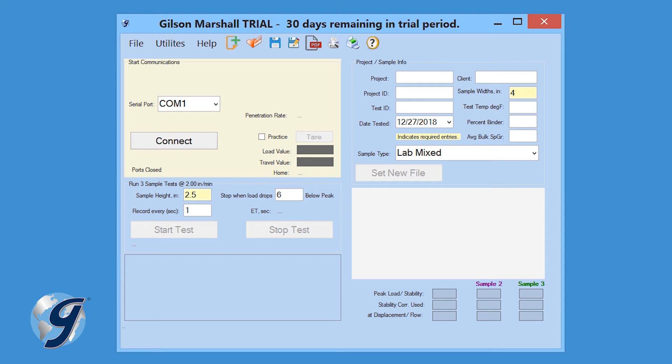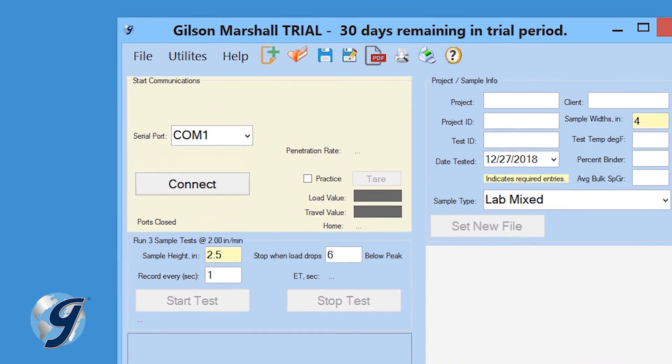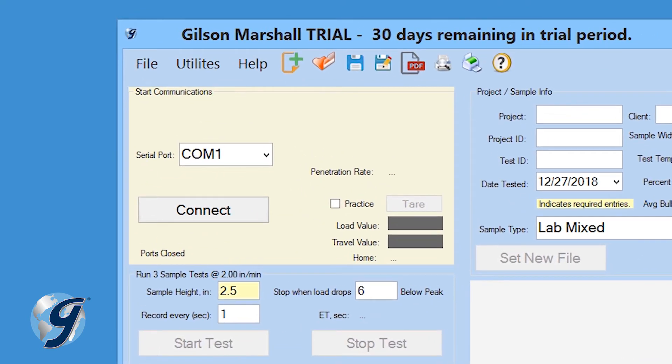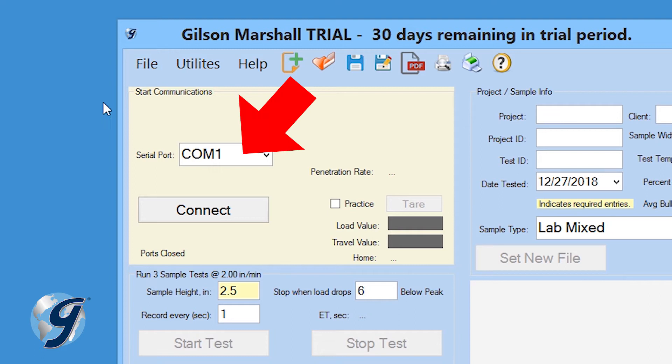Now we are going to connect the computer to the testing device. Make sure the load cell, displacement transducer, and micro-USB connections are secured in the back of the digital readout box. In the yellow highlighted box, Start Communications, select the proper serial port connecting the computer to the digital readout box.